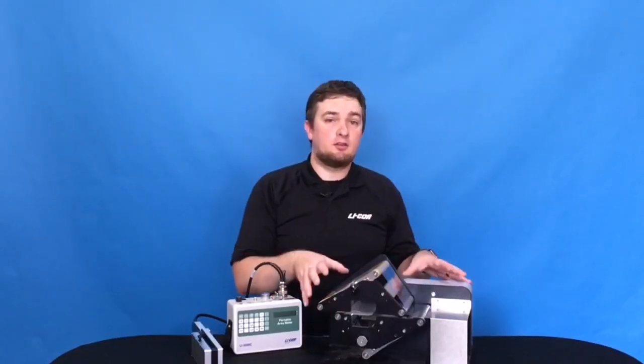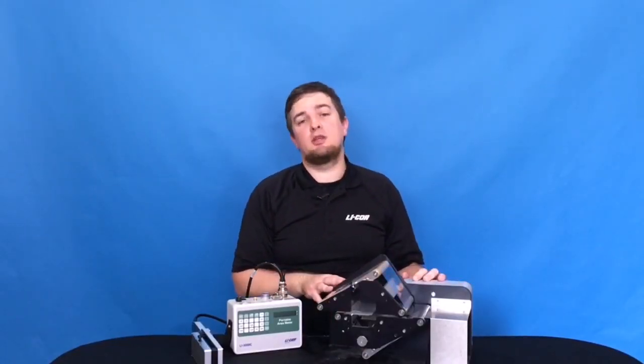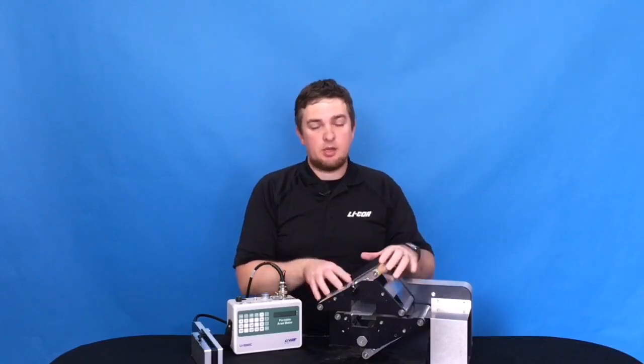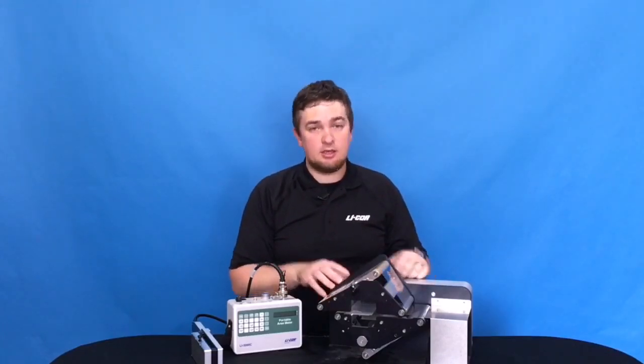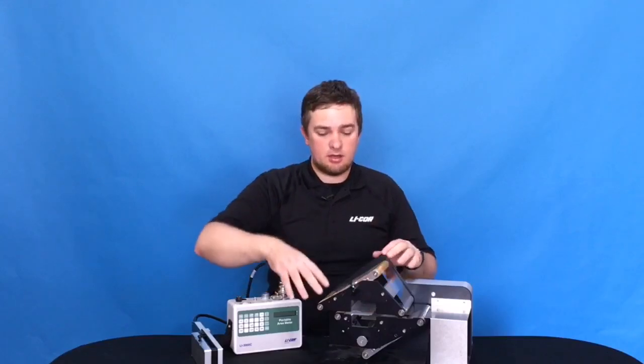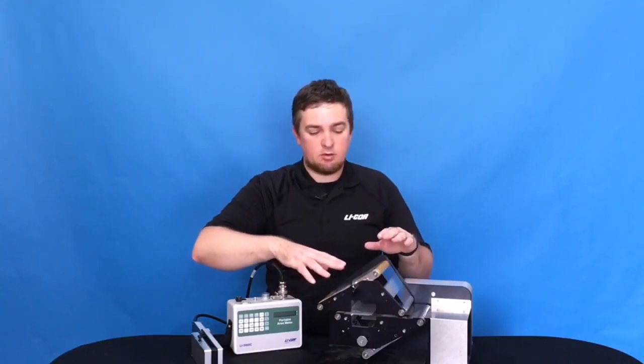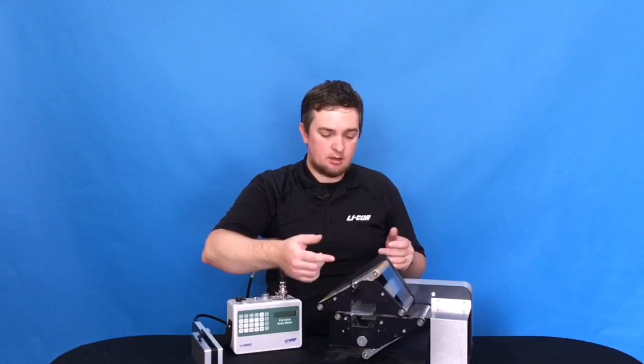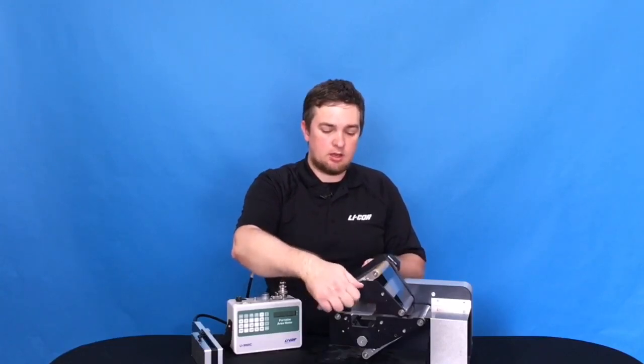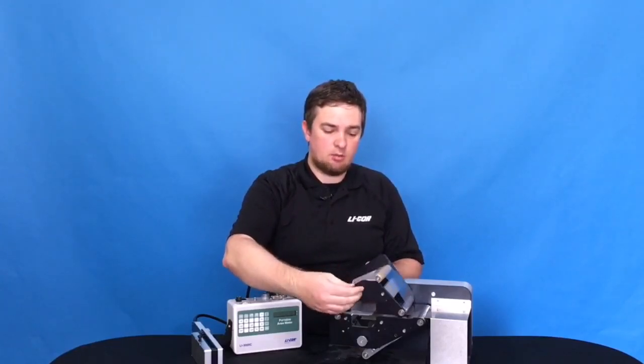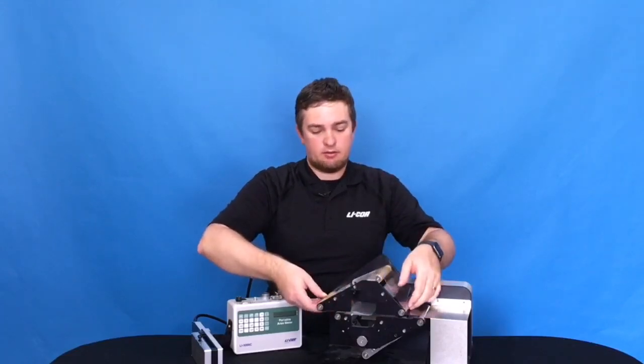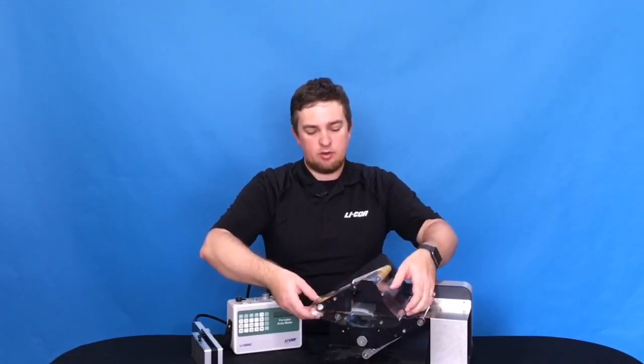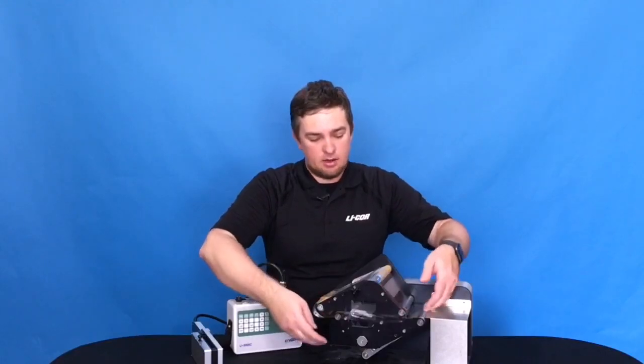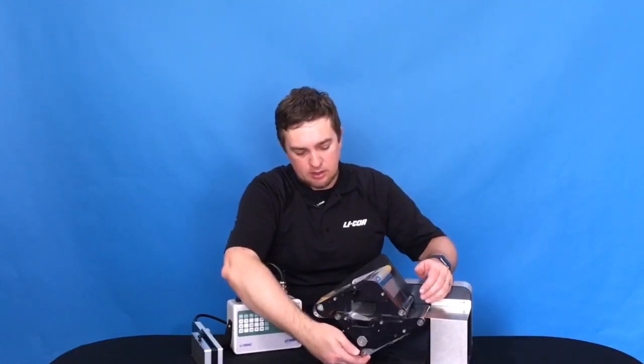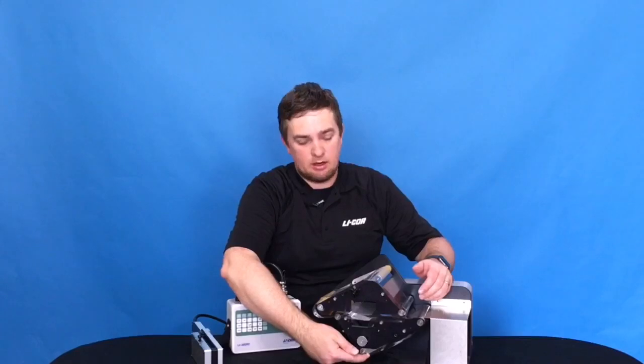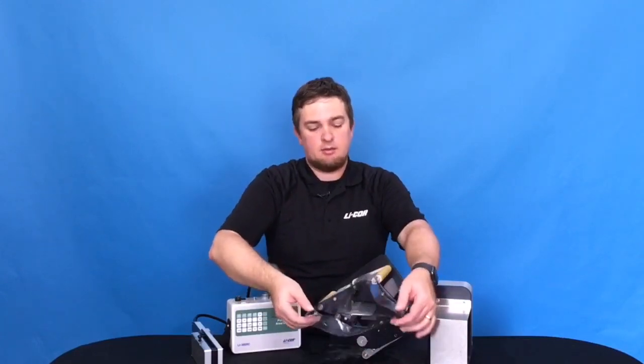If you have the LI-3050C conveyor assembly, there are some things you may need to do as well. The belts may need to be cleaned occasionally. They can get dust or dirt or pollen on them as well. So it's quite simple to remove these belts. For the upper assembly, you would just loosen the pulley here, and that gives you enough flexibility to kind of move the belt off. Same thing with the lower assembly, although you need to lift up on this pulley here and slide the belt off this way.